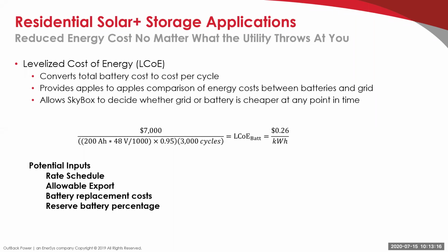The Skybox has an advantage over the Radian in this programming. The batteries the Skybox will work with can be either lead acid, which is traditional, or lithium ion, and the depth of discharge changes. We recommend a 50% depth of discharge with lead acid batteries. With lithium ion batteries, for example SimpliPhi batteries, you can discharge 85%.